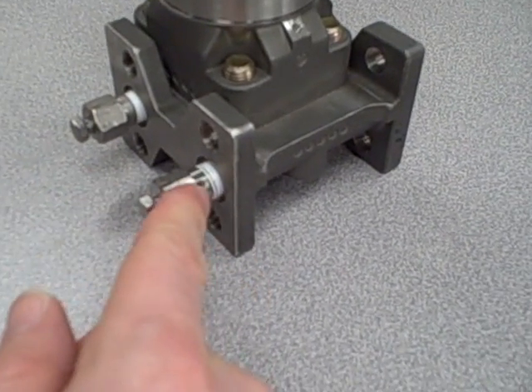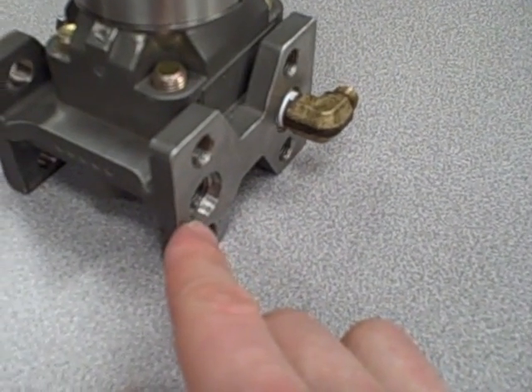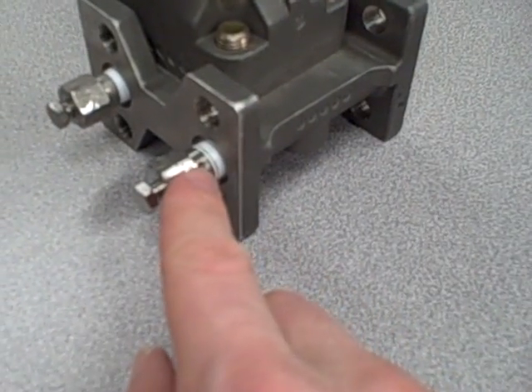It's a convenient method of bleeding off pressure that's better and safer than cracking open a pipe fitting or a tube fitting. Because with a bleed like this, where you have a bleed hole, you know exactly where that pressure is going to vent out.